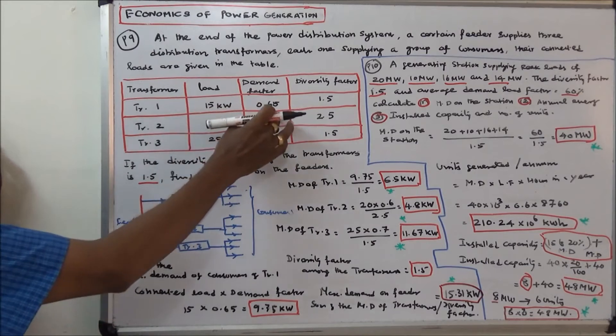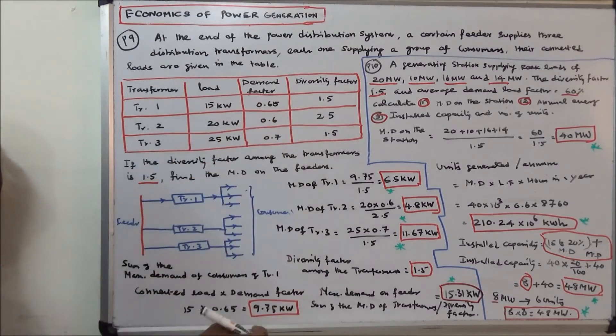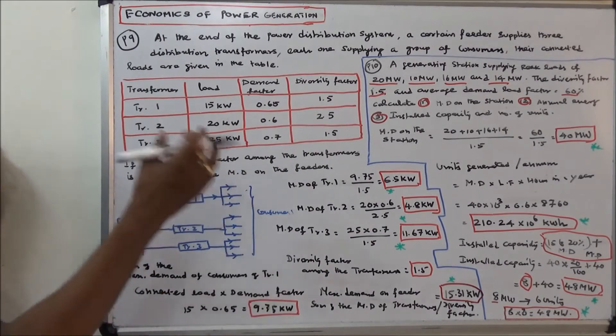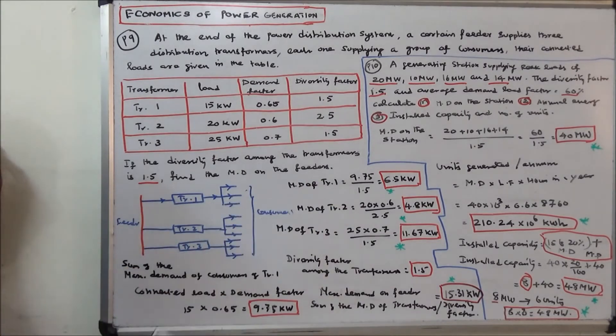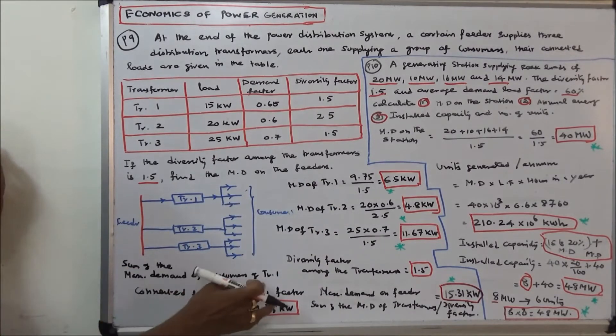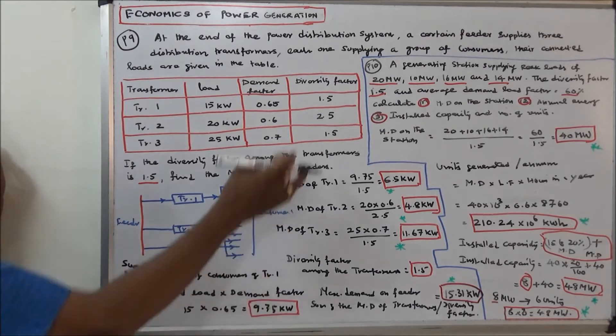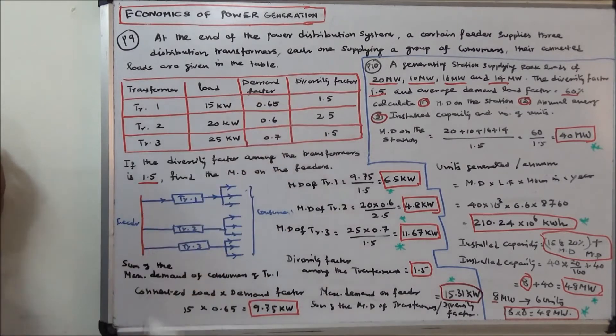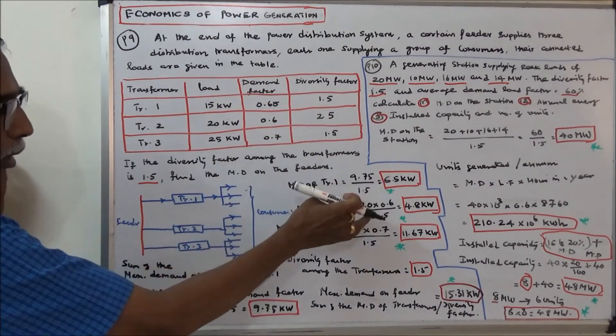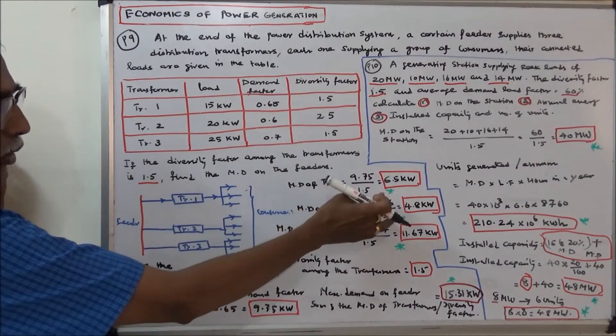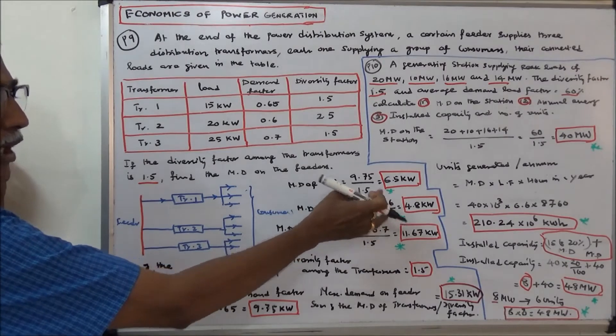That is 15 multiplied by 0.65, which equals 9.75 kilowatts. We then calculate the maximum demand of transformer one, equal to connected load times demand factor divided by diversity factor. So 9.75 divided by 1.5 equals 6.5 kilowatts.